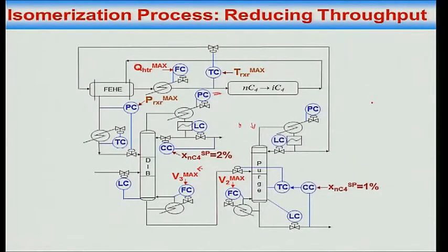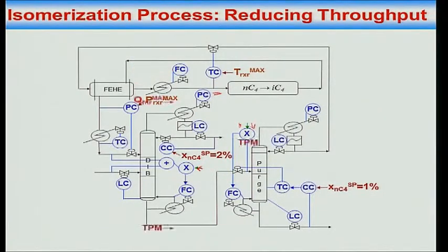As I am reducing throughput, okay, well, I take up ratio control here, and then finally I reduce the throughput using this, right. So boil up is taking up ratio control with respect to the feed to the column, both cases. Both boil ups are maintained in ratio with the feed to the column. That makes sure essentially that you are not unnecessarily consuming too much energy, over boiling.